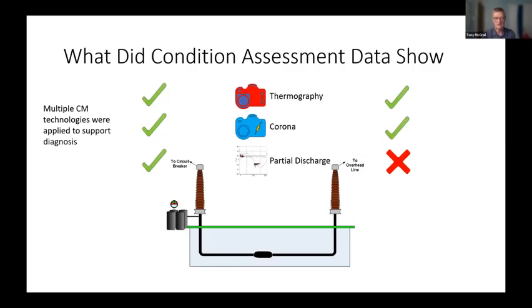Partial discharge using a PD detector, fairly common device. Nothing showing at the circuit breaker end, but at the overhead line end, there was some significant partial discharge. Phase results showed some arcing and sparking. One more, please. Ultrasound didn't show anything while we were there.